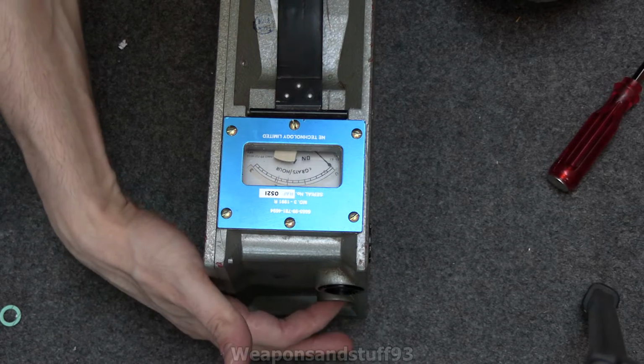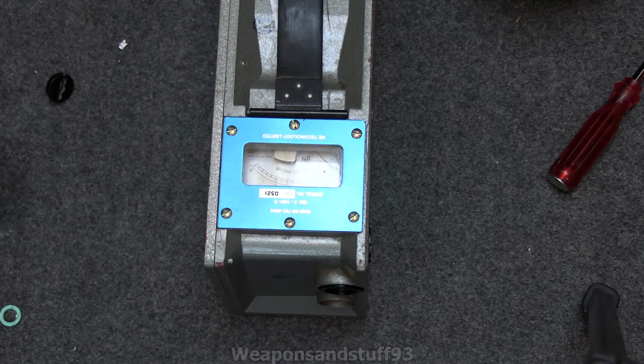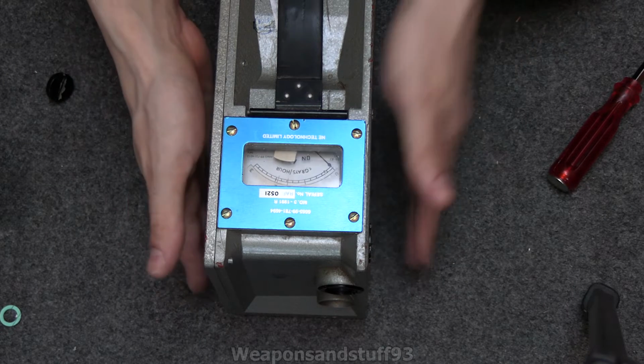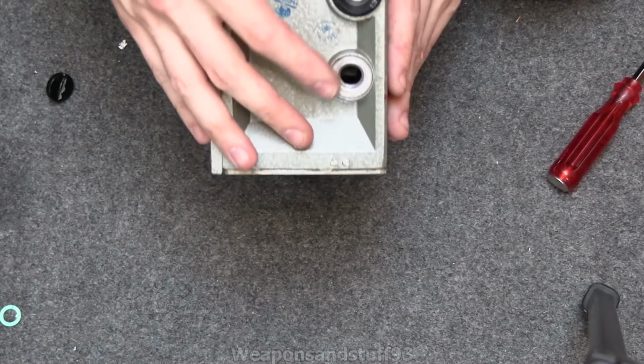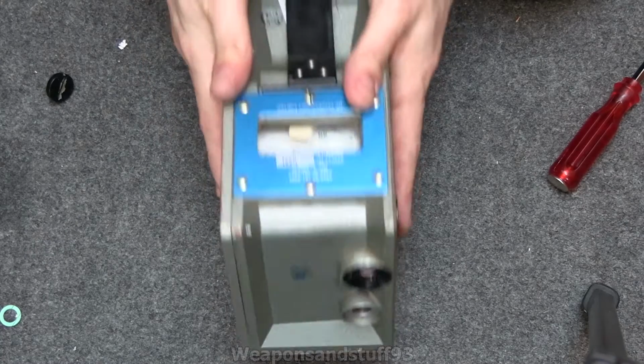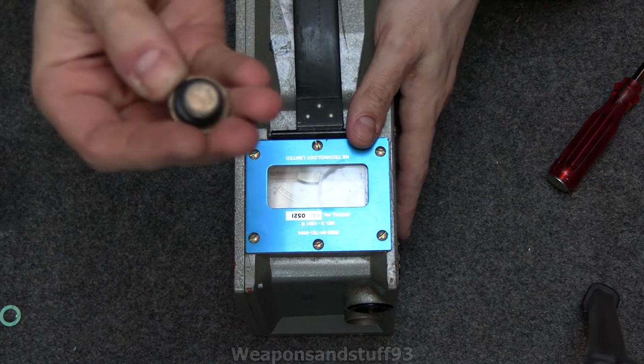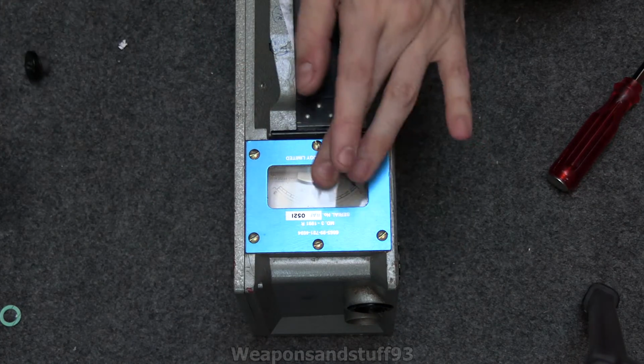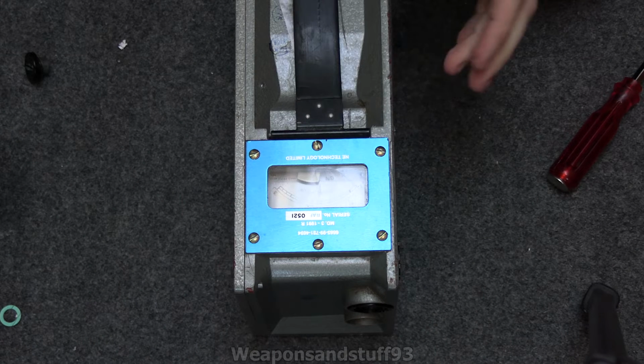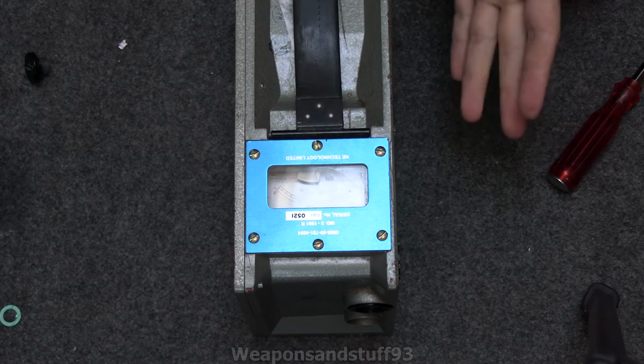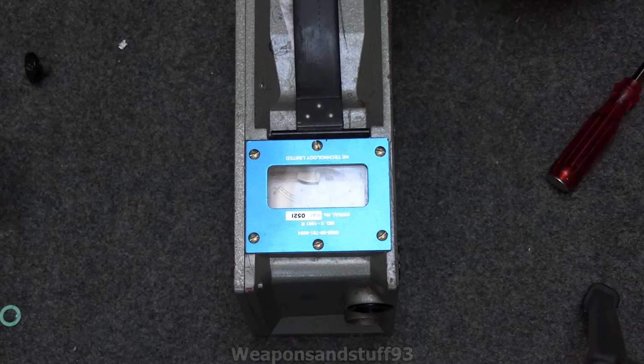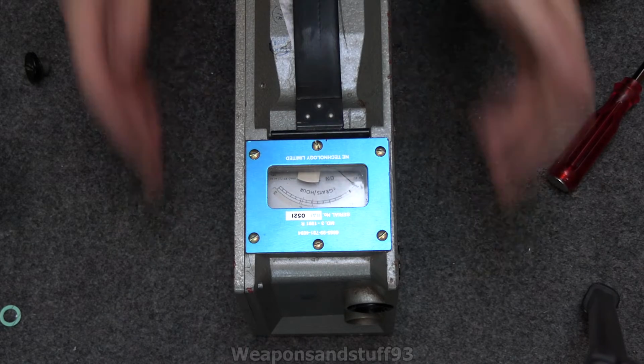Sorry, it's that bottom hole, isn't it? You'd get AM241 or equivalent, generally something that is a strong alpha emitter. Polonium would work as well, I imagine. And what you do is you just simply put that on the top of there or in slightly. You could always blue tack it to this screw cover and then screw it in, and you'll notice the reading will go up and down depending on how close the screw is to being fully screwed in or not, because that's going to be how close the AM241 or whatever is to the ion chamber.